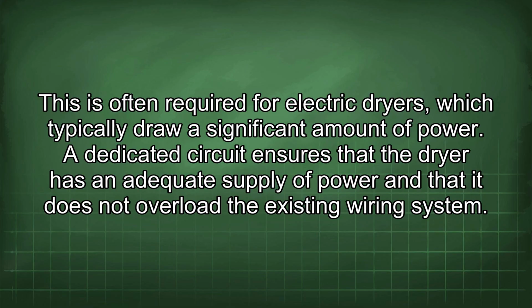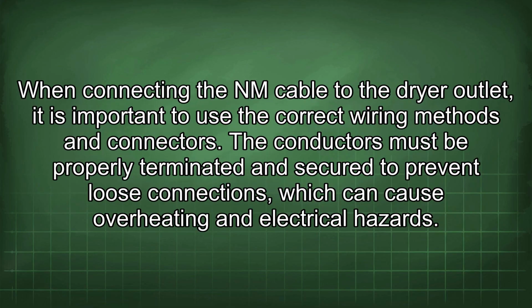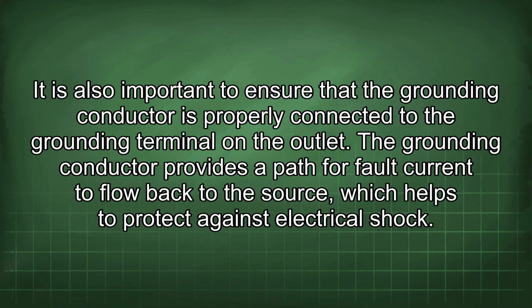When connecting the NM cable to the dryer outlet, it is important to use the correct wiring methods and connectors. The conductors must be properly terminated and secured to prevent loose connections, which can cause overheating and electrical hazards. It is also important to ensure that the grounding conductor is properly connected to the grounding terminal on the outlet. The grounding conductor provides a path for fault current to flow back to the source, which helps to protect against electrical shock.